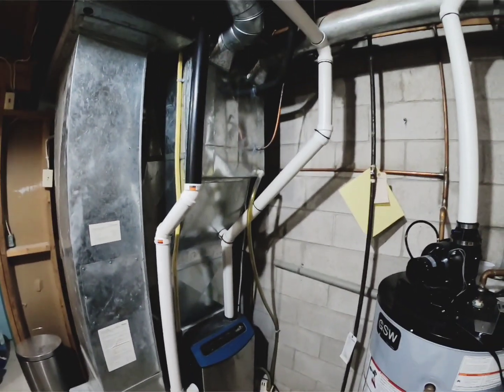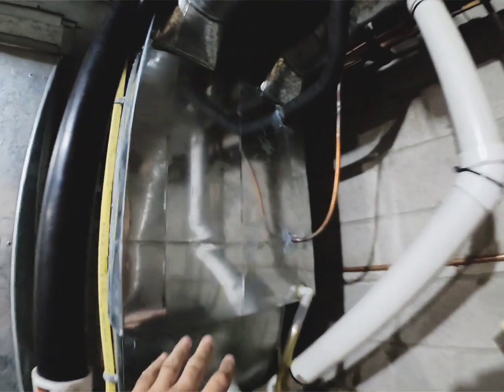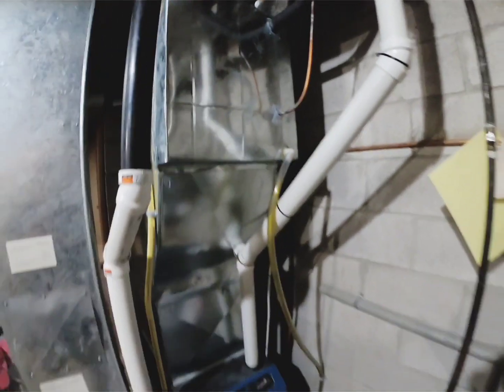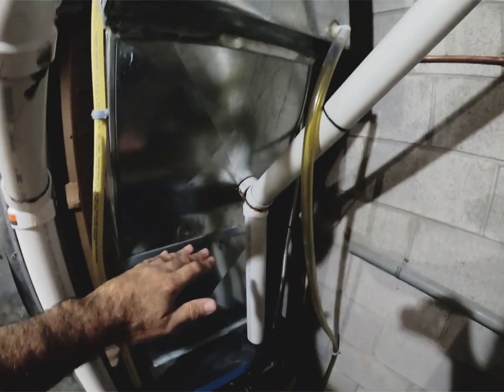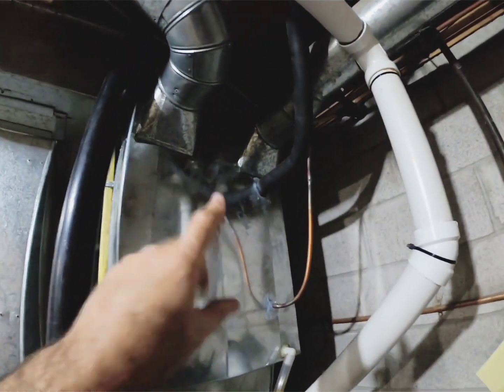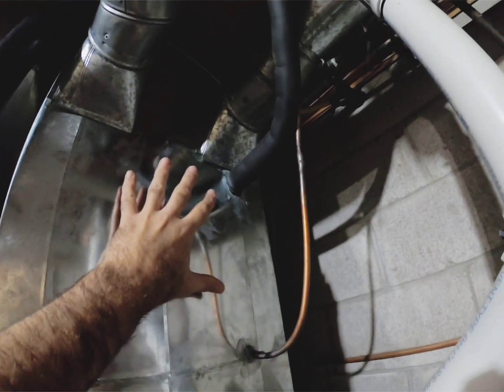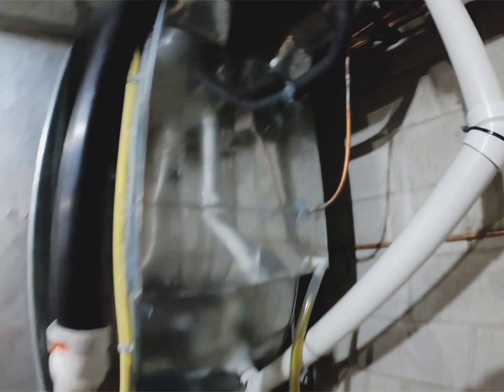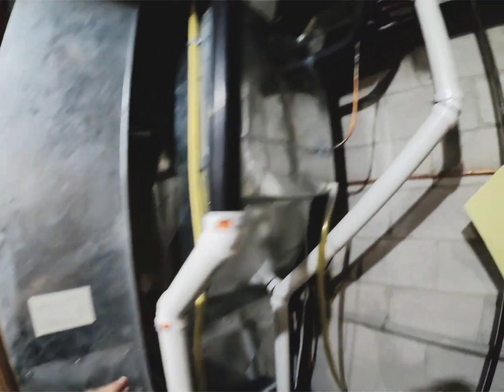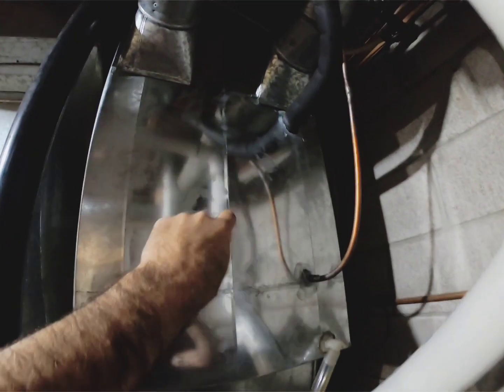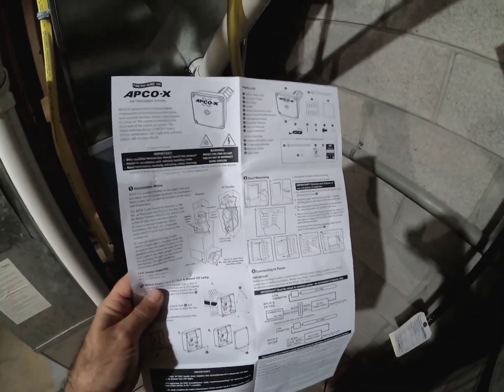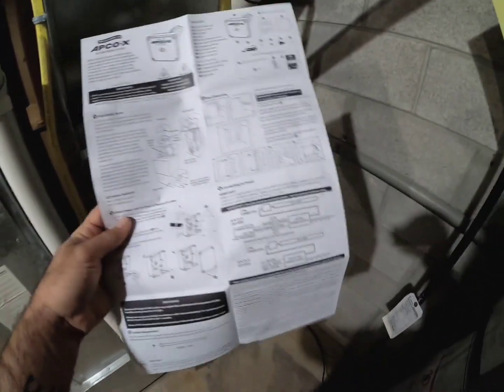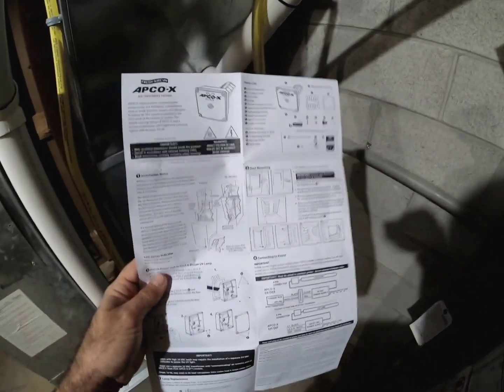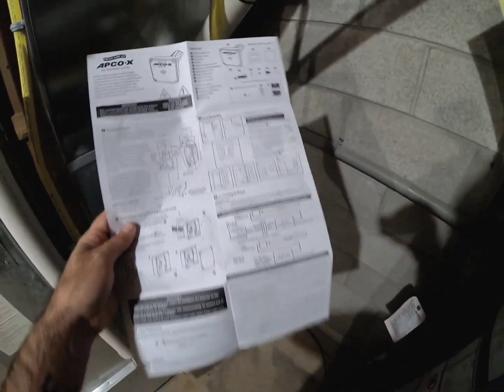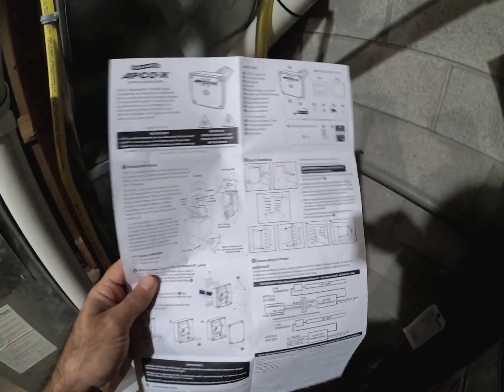So here's our system down in the basement, and as you can see, the A coil is mounted quite a bit higher than you would normally see it. You'd normally see it slightly above the furnace, and it's at the top of our supply plenum, so we can't install the full APCO-X system here or above it. So we're going to install it on the return side, and I'll get to that in a minute, and then we're going to install the remote bulb either underneath the A coil or slightly above it, wherever the best placement is. So obviously reading the manual is key before we start any installation. I would suggest you take 15 minutes or so and read this manual front to back and make sure that you have everything you need and you're going to install it correctly.